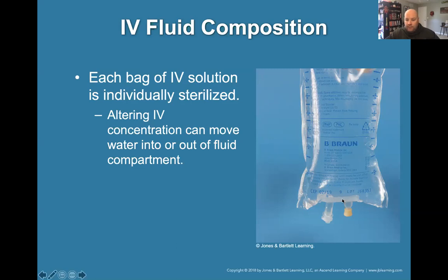If you look at the bottom, there's 2 ports. Very important to understand that there's 2 ports, and you may have already seen them. Some of you may know what they do, and a lot of you may not. The longer port on the left, this is where you plug in the end of your drip chamber. You guys have probably done that or seen that. Pull the cap off, you stab the drip chamber up in there.